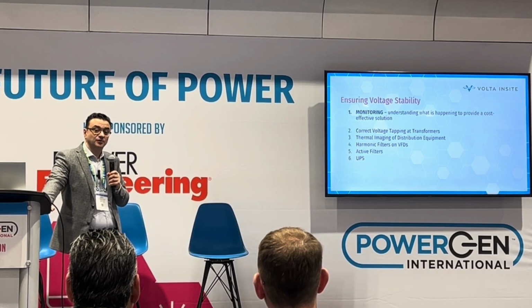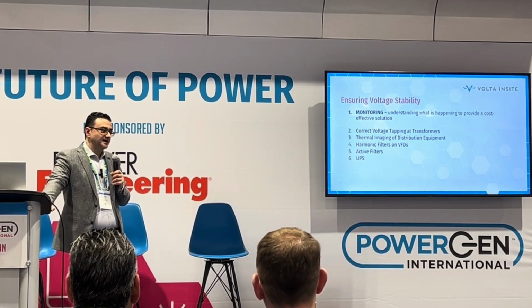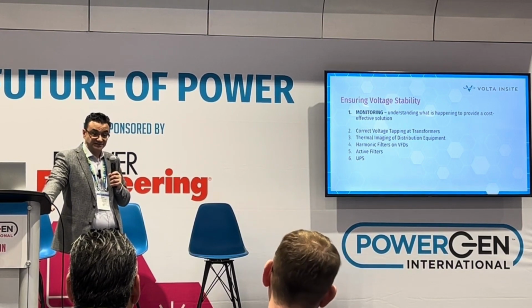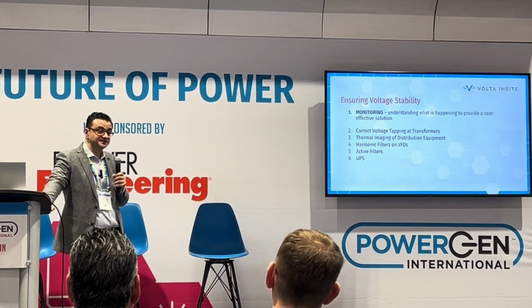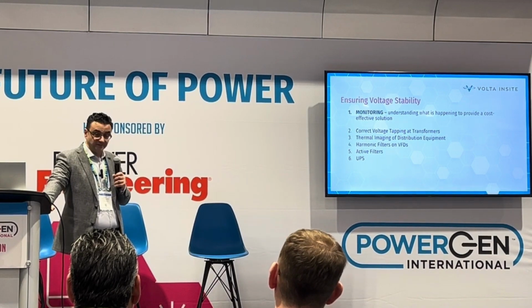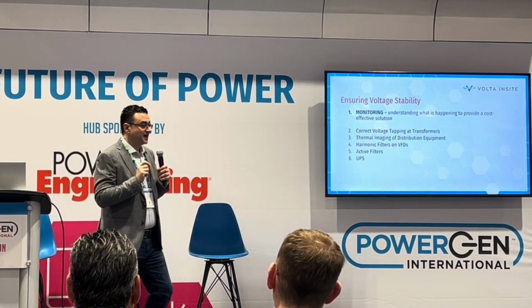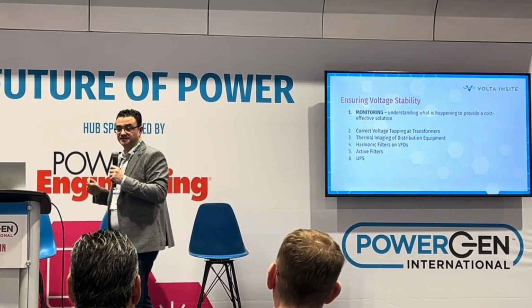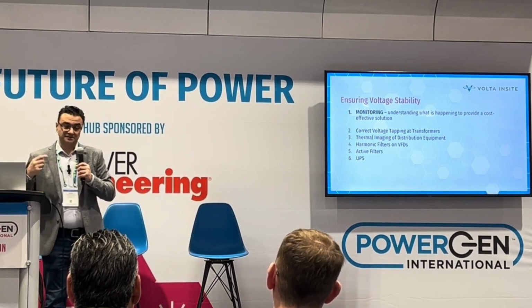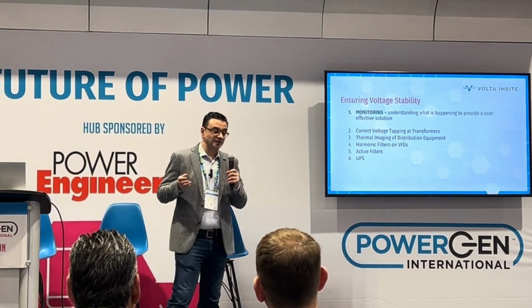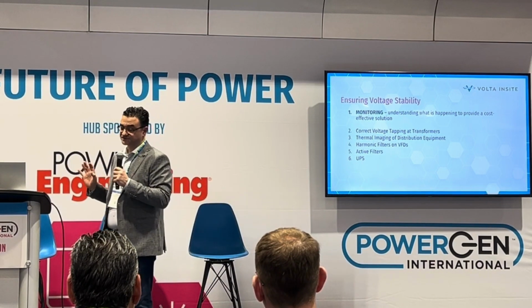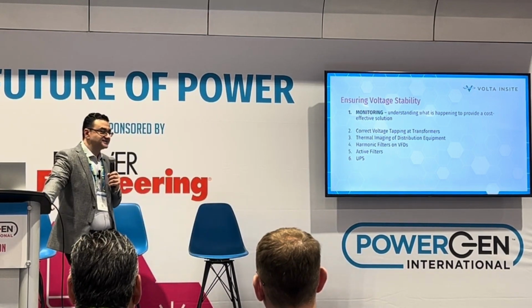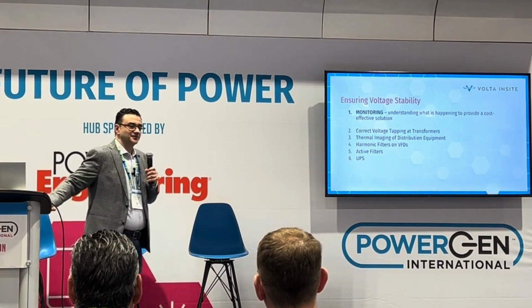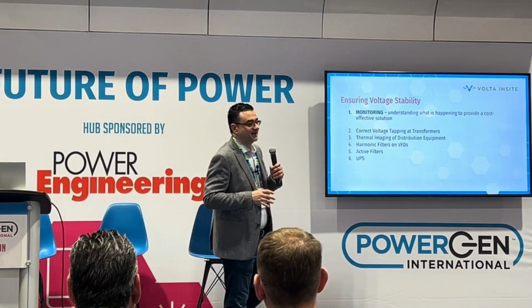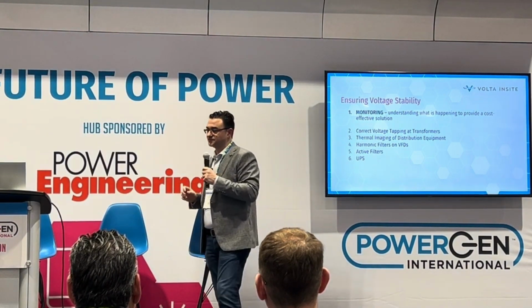There was a 300 horsepower motor, a pumping facility. And under utility power, there was a motor that was running just fine. They had decided to deploy a VFD to run that particular pump. And the VFD would run the pump under utility power. But as soon as they would switch over to backup generation, the pump would kick up, the VFD would start running, and eventually after about 20 seconds, it would kick out without ever reaching full speed. So when I got on site, all the electricians were talking about, oh, this is a ghost electrical problem. The generator can't handle this type of load with switching frequency and so forth.